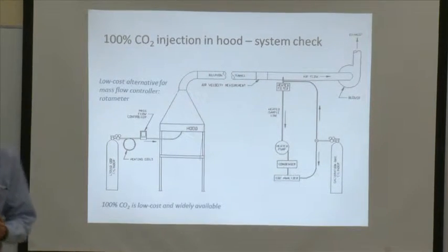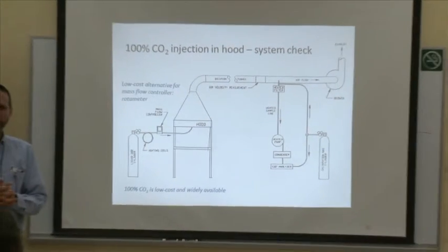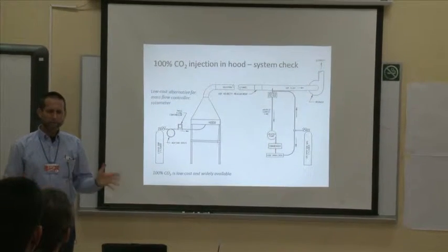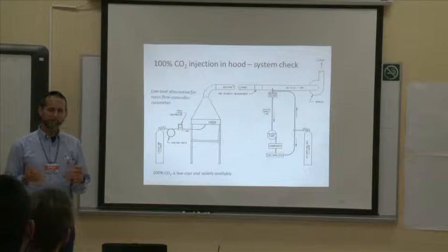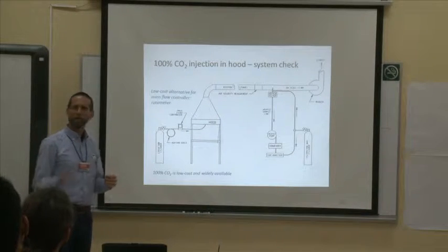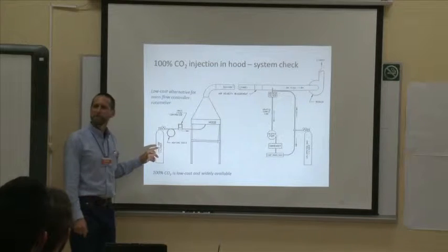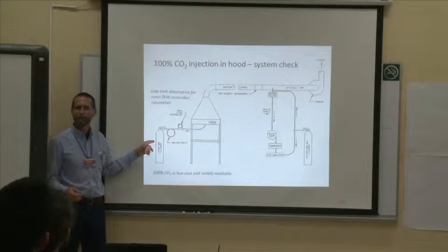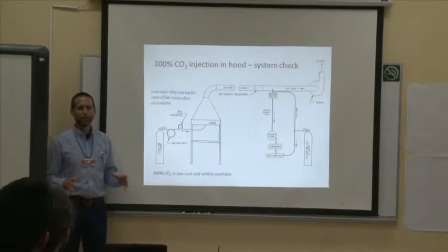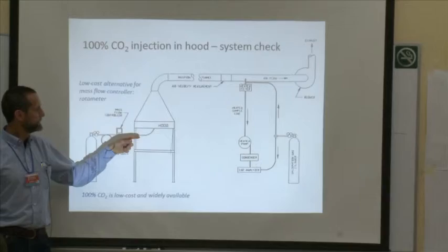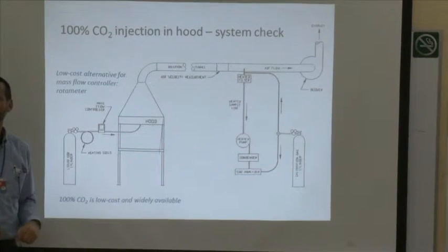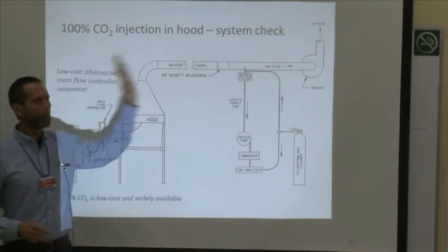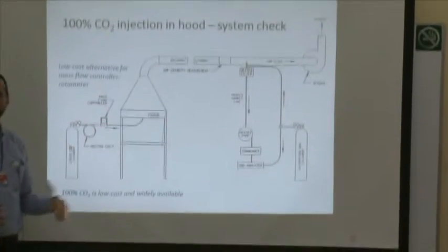Okay, so while we were trying to figure out what the problem was, we got to the point where we just could not figure out the problem. And then Seth had a great idea, okay? And I think this is a great idea, and I want to make sure to give Seth credit for this. He said, what if we took some CO2 that was 100%, and what if we just injected the CO2 at a known flow rate directly into the hood, that then tests the whole system, you know, that tests everything all at the same time.